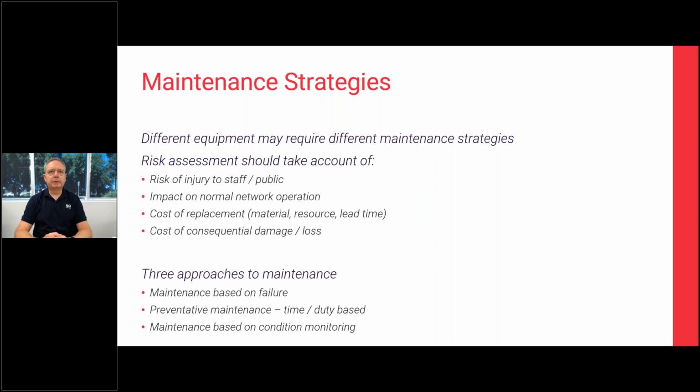If we were to lose a particular cable or switchboard and can't get it back in for a period of time, how much production have we lost, and how much is that going to impact the network? Maybe in a petrochemical plant in the wrong place, it caused major disruption through the network. That's typically what you would do for all the assets.